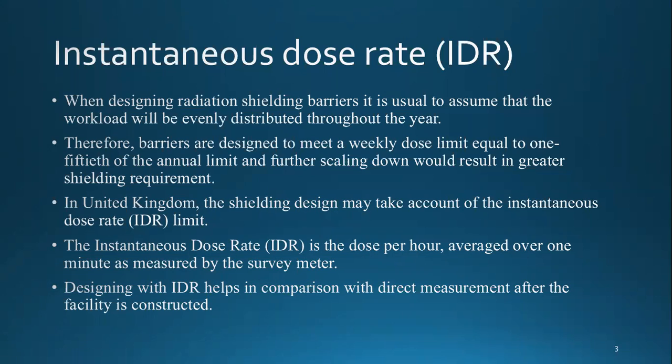What is the advantage of this? Designing with IDR actually helps in comparison with direct measurement after the facility is constructed. What is IDR? IDR is the one that you measure when you do the final survey. That value should be equal to the one that you used for designing if you are using IDR. Then it is easy to compare. This is what I designed with, and now I am getting the same value. So that way, instantaneous dose rate is quite helpful.